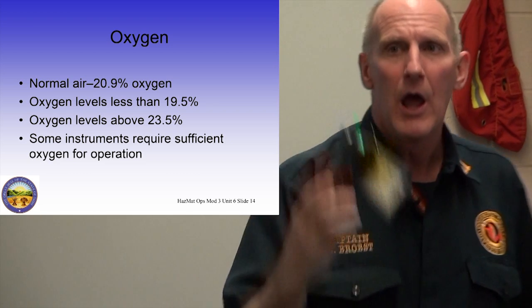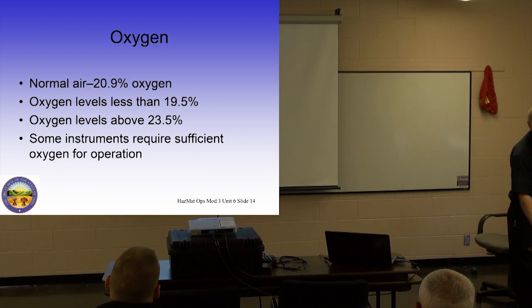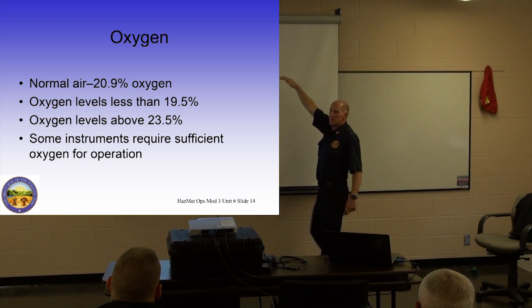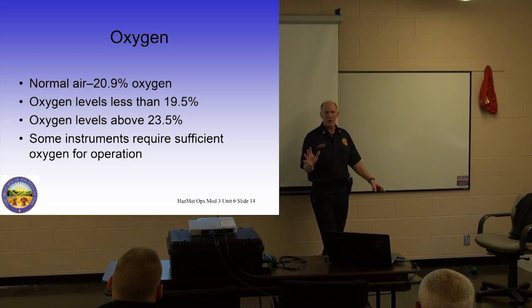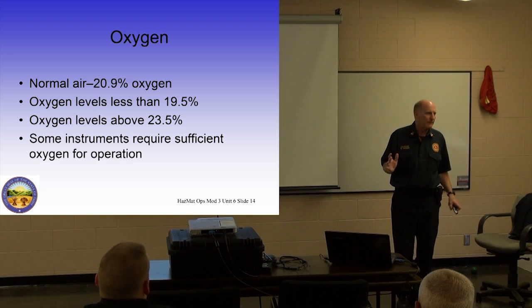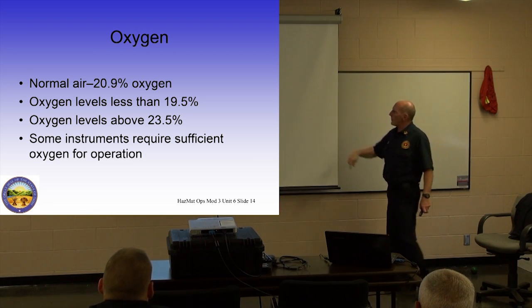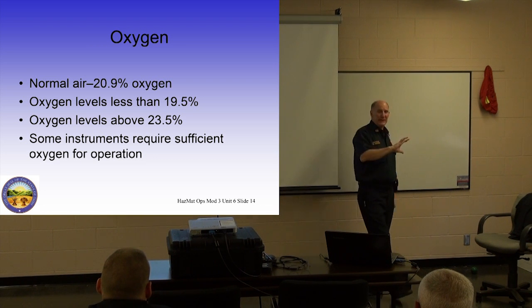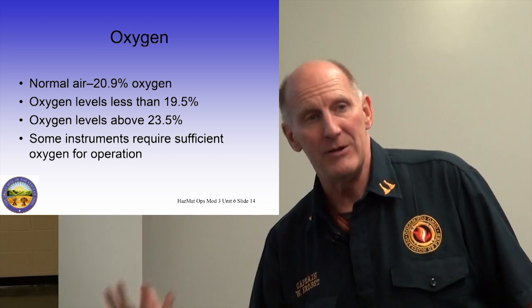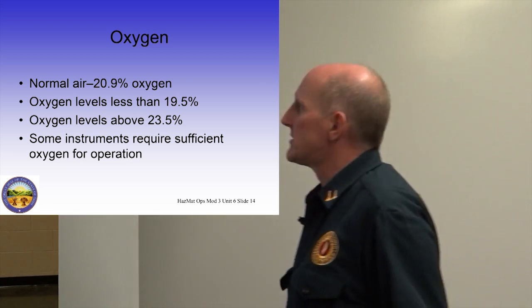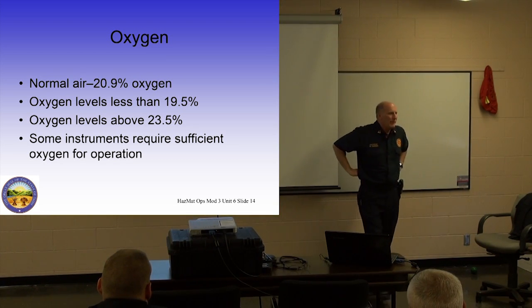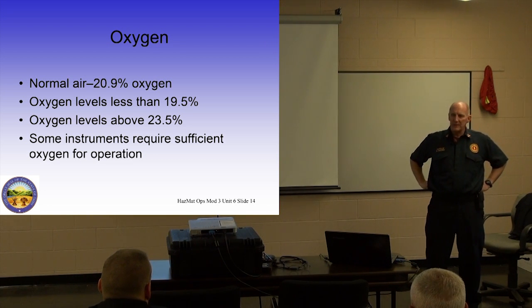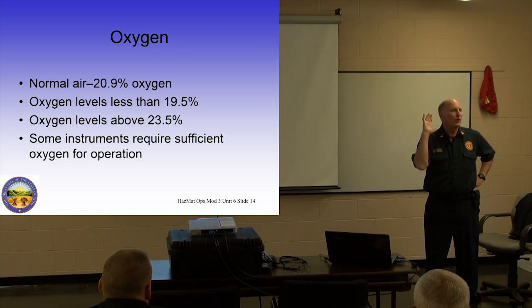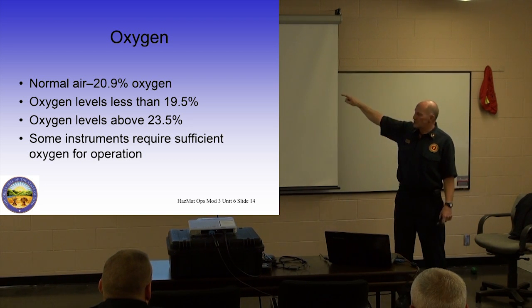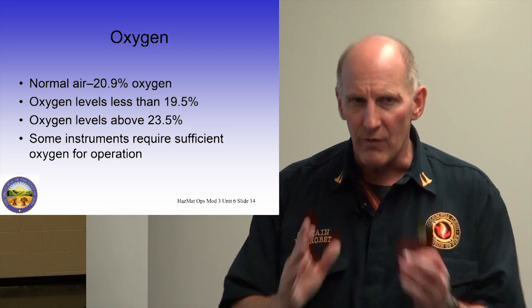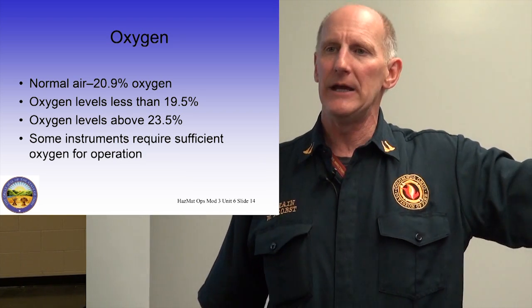When you turn this thing on, when it fresh air calibrates, it should go to 20.9%. Don't get confused. There's other instruments out there that instead of going to 20.9 will go to 21. It doesn't matter. It's close enough. 2 levels. The alarm will go off when oxygen depletes, and the alarm will go off when oxygen enriches. So there's 2 alarm levels on this instrument. Low O2 is 19.5%. The reason it goes at 19.5% is because of an OSHA law. OSHA says when O2 reaches 19.5%, this product is IDLH.